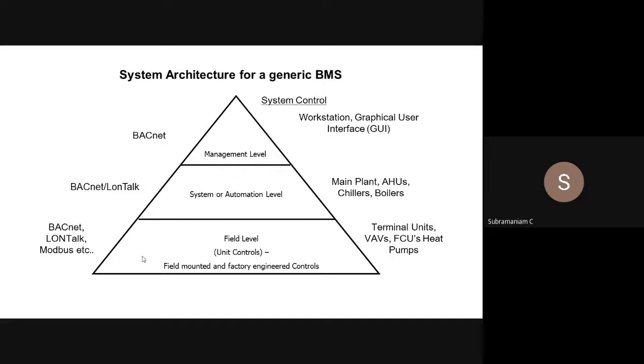So controllers can be BACnet controllers. When we get a controller, it's not the manufacturer which is important. We can buy from manufacturer X, and after 3 years, if we want to replace some controller, we can buy that from somebody else also. We don't have dependency, right? The owner is not locked to one supplier, one vendor. That is the advantage of having an open system architecture. So we follow BACnet at the system level, and at the unit level, either LON or BACnet over IP.